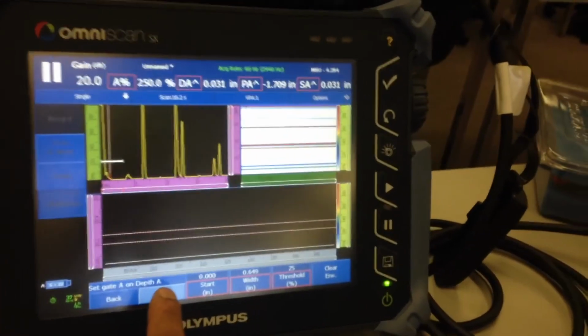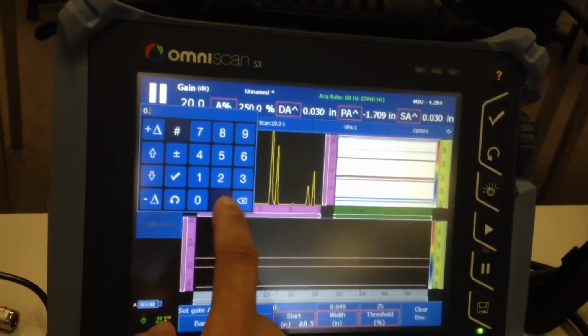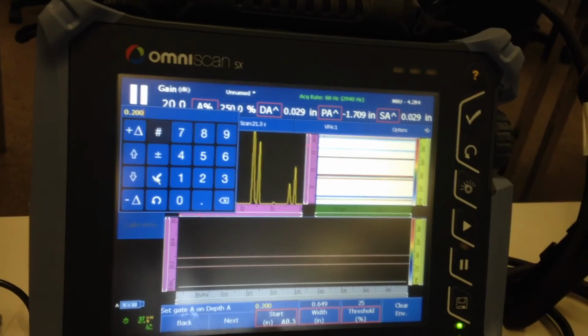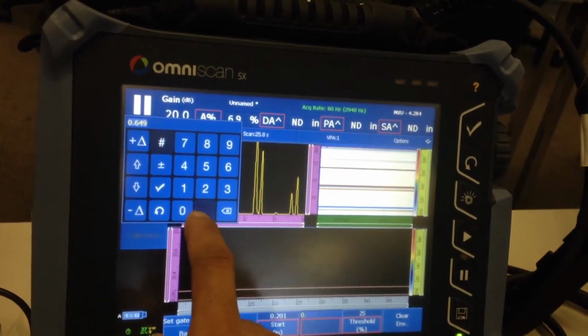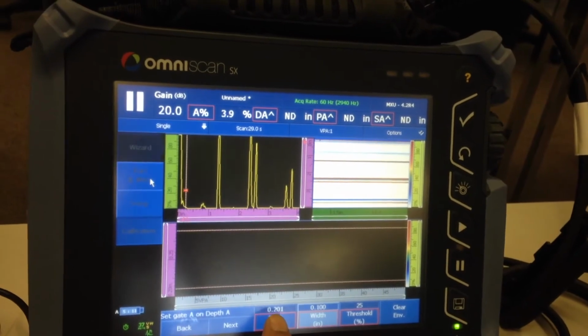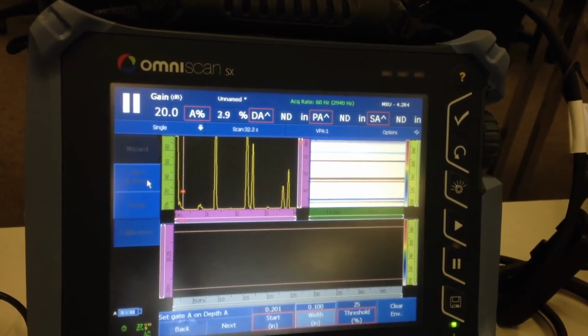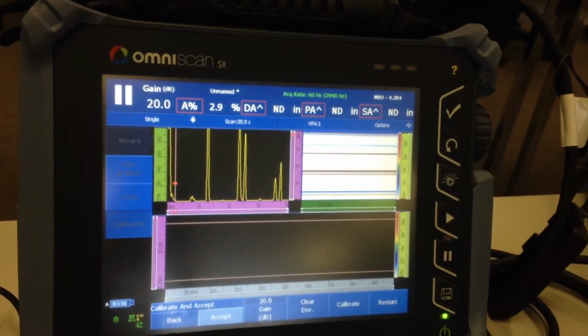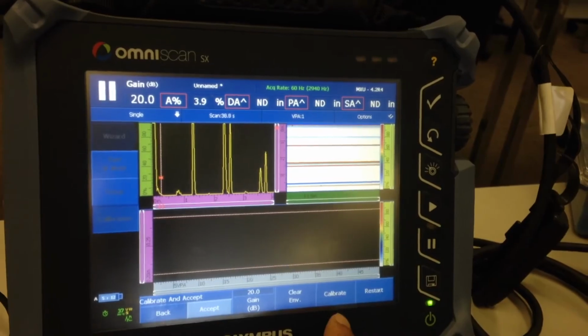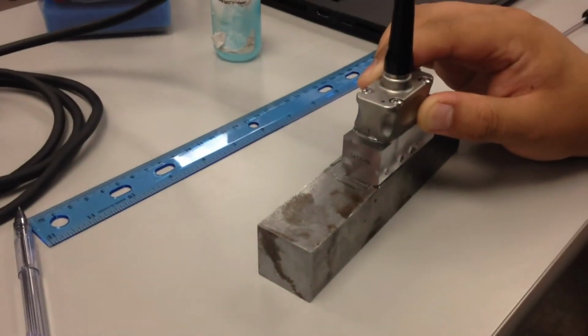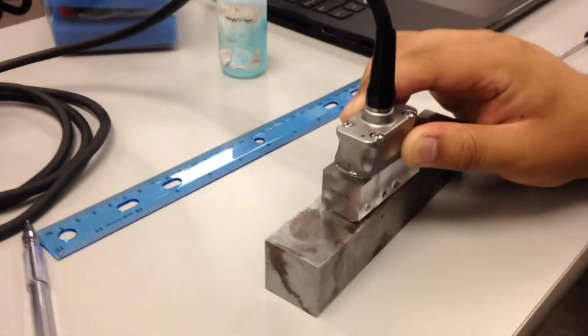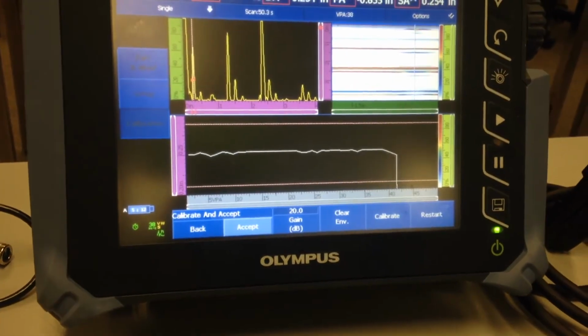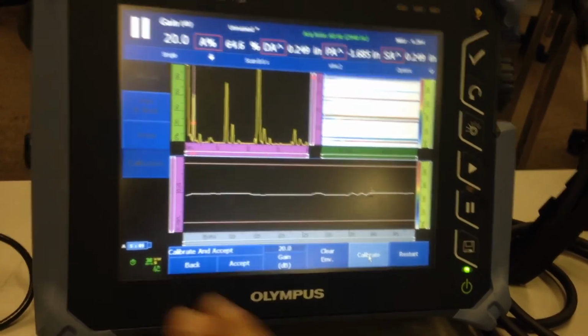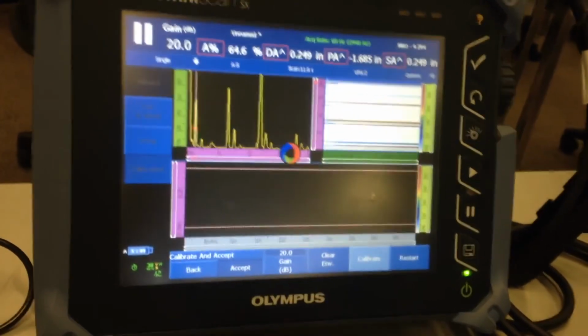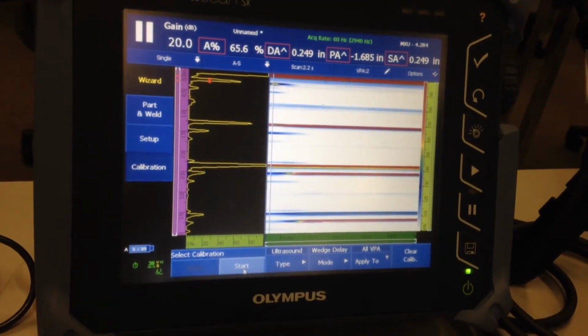So I'm going to start my gate a little before 1/4 inch. And width, which will take it to a little bit after 1/4 inch. So that would be 0.1. So now my gate is from 0.2 to 0.3. Click Next. Once I see my calibrate screen, I'm ready to put some couplant on the calibration block and get a signal from the 1/4 inch side drill hole. Once I get that, click Calibrate and get a signal again. Once I get a nice straight line, I hit Accept. I'm done with my wedge delay calibration.